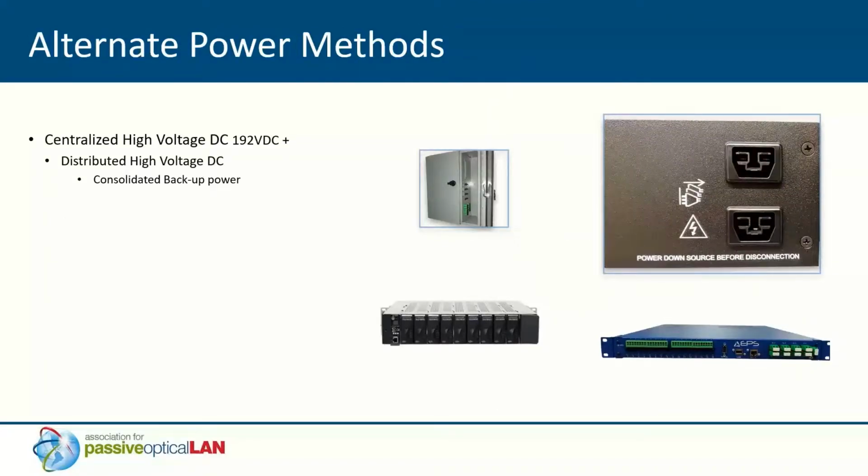I talked a little bit about the high voltage DC. I just want to dive into that just a little bit more. We're seeing more and more buildings having a DC grid, if you will, so a centralized DC plant. I think Steve showed that also in the stadium example, where they have a high voltage DC, and that feeds the MDFs with 192 volts plus.